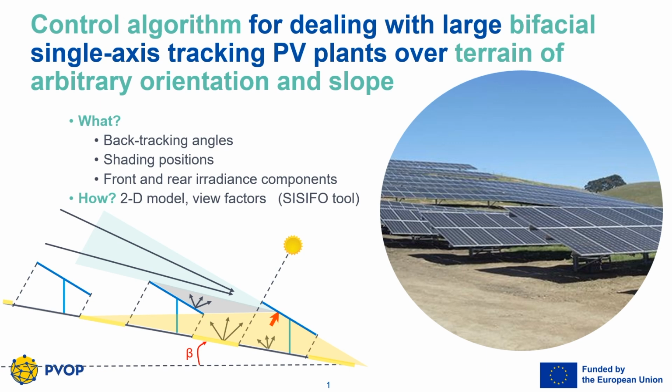Backtracking is well known in PV plants located on horizontal terrain. But how does it compare to plants on sloping terrain? This case eliminates earthwork costs and allows for installation in more locations. However, it causes a loss of production because the terrain blocks part of the sky.